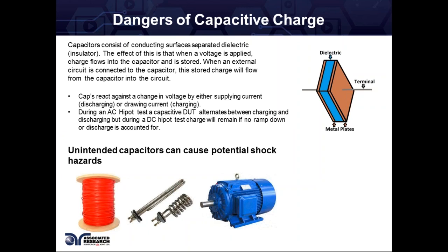Capacitors consist of conducting surfaces separated by a dielectric material. When voltage is applied, current or charge flows into the capacitor and is stored, just waiting for something to discharge it. Capacitors react against a change in voltage — a change in voltage is where the danger is, because it's constantly charging by drawing current or discharging by supplying current. During an AC Hipot test, you can get away without a ramp down because it's constantly charging and discharging, so ideally at the end there's not much charge left. We also have a discharge circuit at the end of all Hipot tests which, if you're within our capacitive loading specs, we promise to discharge your DUT by the time your test is over.